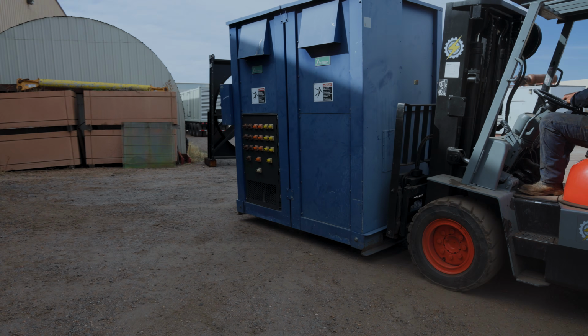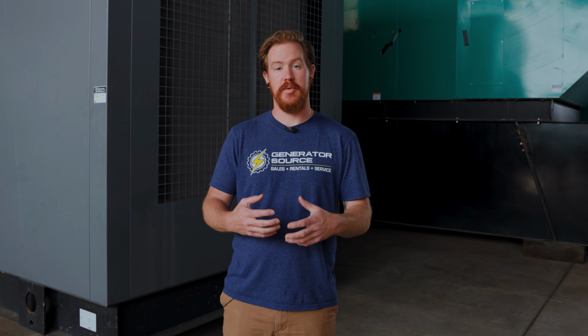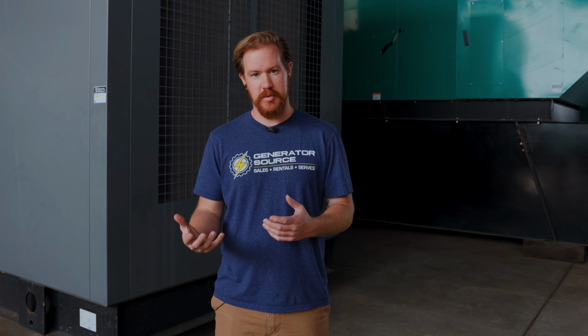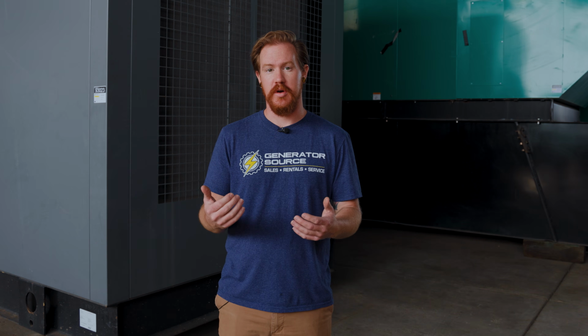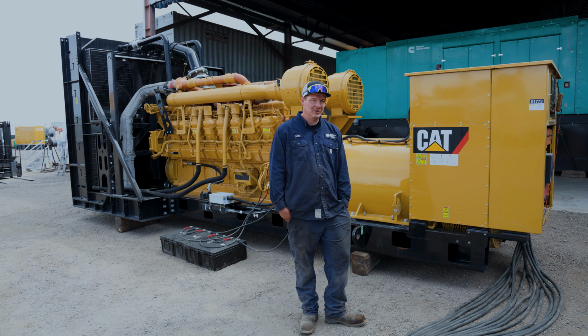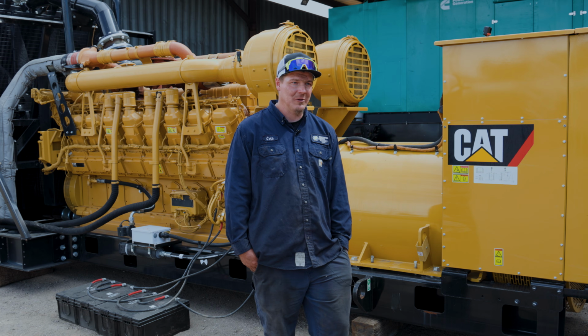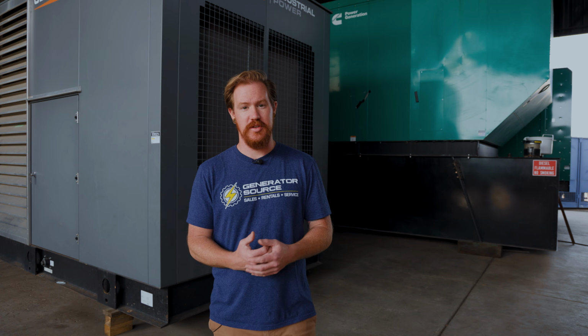If a generator is unable to come up to an actual operating temperature due to no or light load scenarios, it never actually has the opportunity to build up enough heat to burn off excess carbon inside the engine or excess fuel inside the exhaust system. So in this regard, an exercise schedule could actually be detrimental to the health of your unit. The load bank test really ensures that your generator is going to perform to its maximum capability in case of an outage. The ugly truth is you don't really know where your maintenance plan could be failing until you stress the unit and see what breaks.